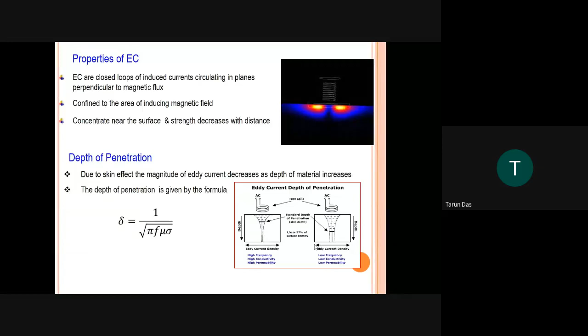Rather, the depth that eddy current penetrates into the material is affected by the frequency of the excitation current and the electrical conductivity and magnetic permeability of the specimen. The depth of penetration decreases with increasing frequency, conductivity and magnetic permeability. The depth at which the eddy current density has decreased to 1/e, as you all know, about 37% of the surface density, is called the standard penetration depth.